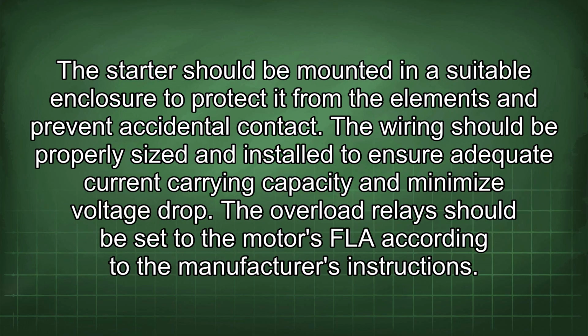The starter should be mounted in a suitable enclosure to protect it from the elements and prevent accidental contact. The wiring should be properly sized and installed to ensure adequate current carrying capacity and minimize voltage drop. The overload relay should be set to the motor's FLA according to the manufacturer's instructions.